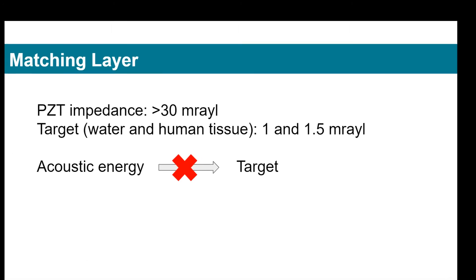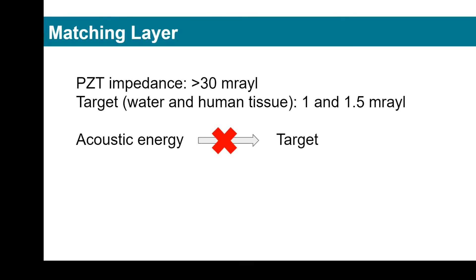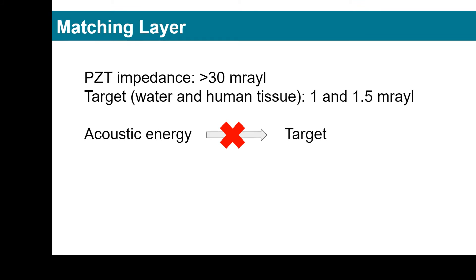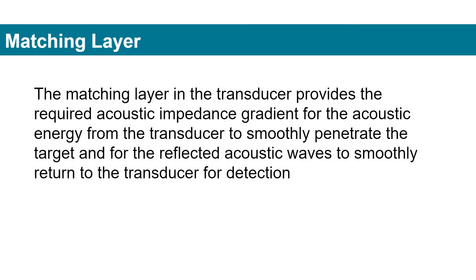Transducers are based on PZT ceramic or single crystal material, which have a high acoustic impedance above 30 MRayl. Targets such as water and human tissue have much lower impedance of 1.5 MRayl and 1.7 MRayl correspondingly. If we use the PZT transducer directly on the target, the acoustic energy will only be reflected on the surface of the transducer and not penetrate the target. Therefore, we need matching layers in the transducer to provide the required acoustic impedance gradient, for the acoustic energy to smoothly penetrate the target, and for the reflective acoustic waves to smoothly return to the transducer for detection.